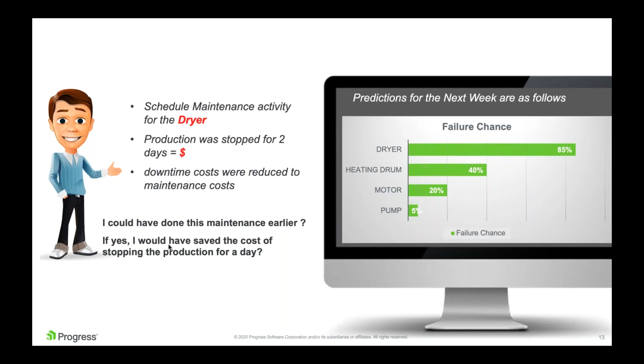Now he tries to figure out what if this solution triggers an alert after a month and says, okay, heating drum fails now. They can't go on doing repetitive maintenance based on these predictions. So they dig down into the solution, and they figure out that there are 4 sensors that are critical for the process. These 4 sensors are, let's say, exhaust air temperature, exhaust RPM, vibration, and outlet temperature.